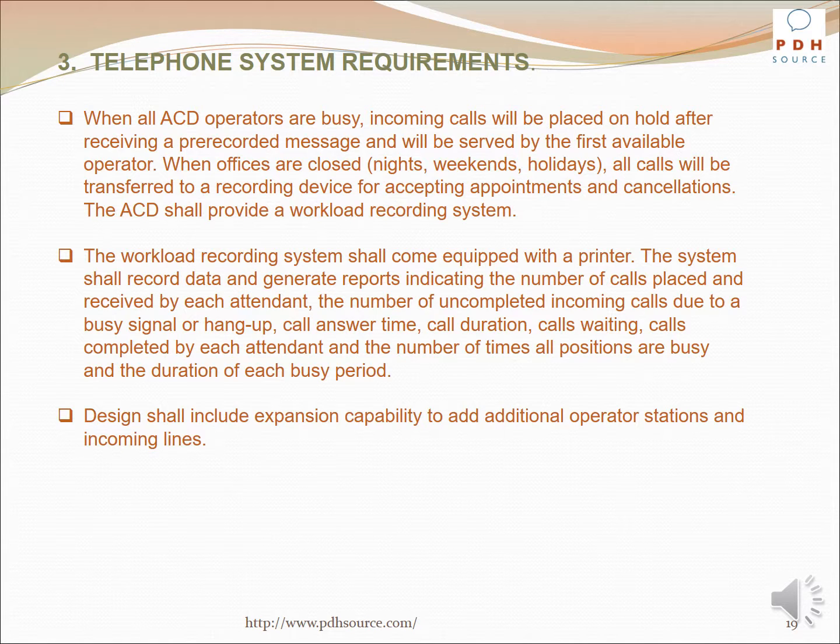The system shall record data and generate reports indicating the number of calls placed and received by each attendant, the number of uncompleted incoming calls due to a busy signal or hang-up, call answer time, call duration, calls waiting, calls completed by each attendant, and the number of times all positions are busy and the duration of each busy period. Design shall include expansion capability to add additional operator stations and incoming lines.